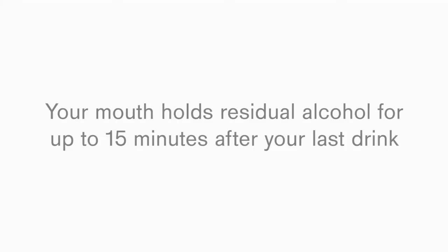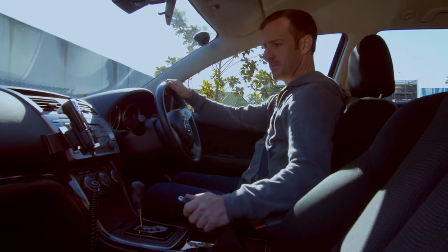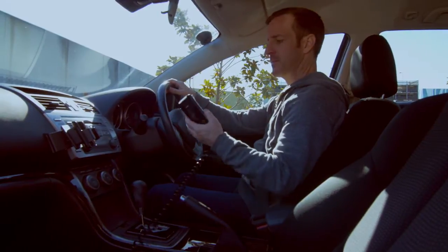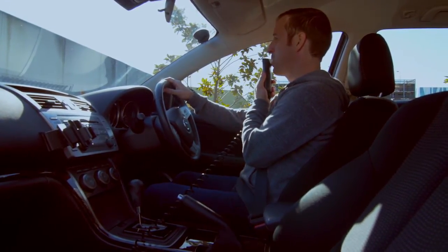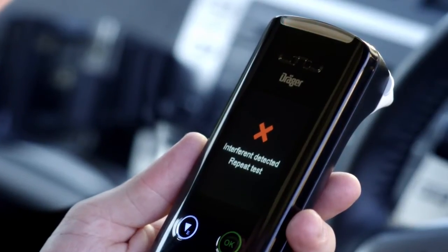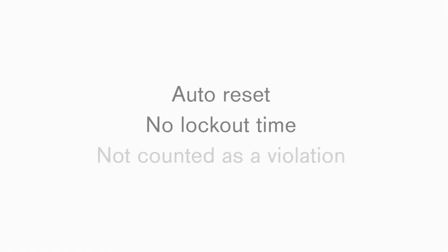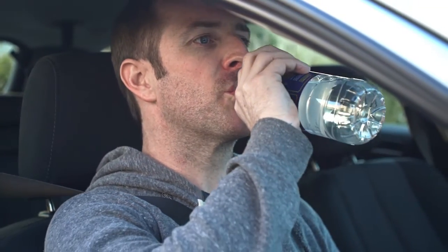Your mouth holds residual alcohol for up to 15 minutes after your last drink. It's important that you wait 15 minutes prior to testing. The Draeger Interlock 7000 can differentiate between mouth alcohol and breath alcohol. In case mouth alcohol is detected from food or drink, the message INTERFERENT DETECTED REPEAT TEST will appear. The device will automatically reset for a new test with no lockout time and without this being considered a violation of the program. Ensure to keep a bottle of water with you and rinse your mouth out before using the Interlox 7000.